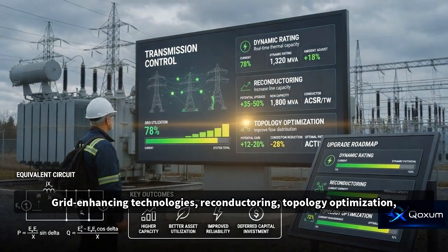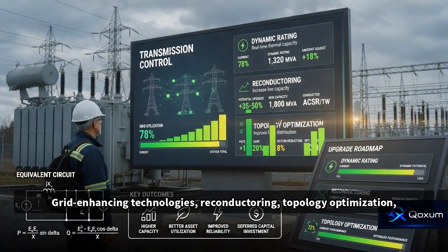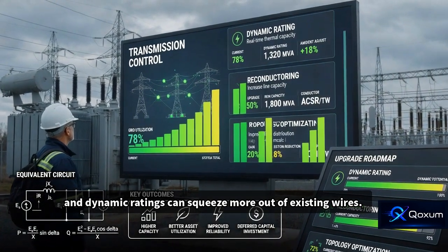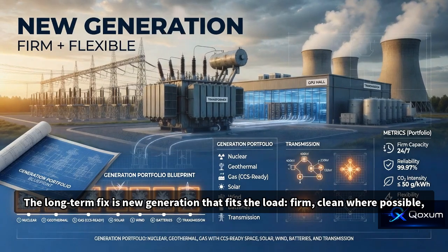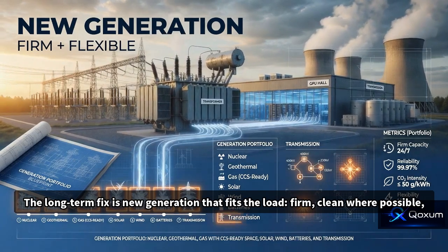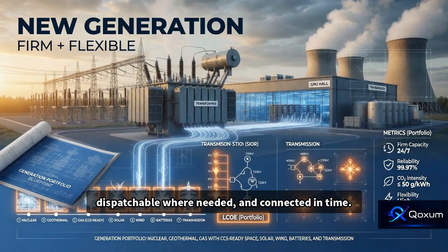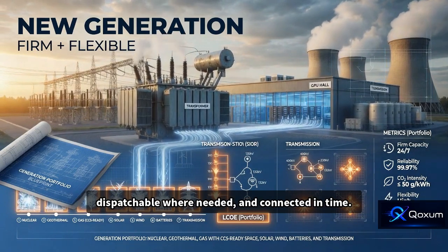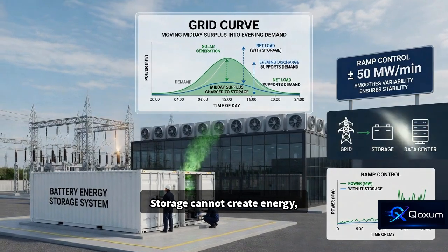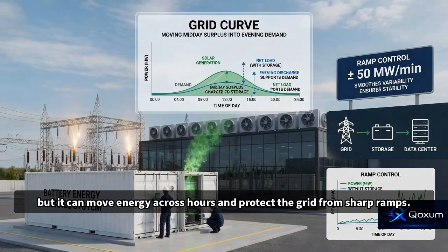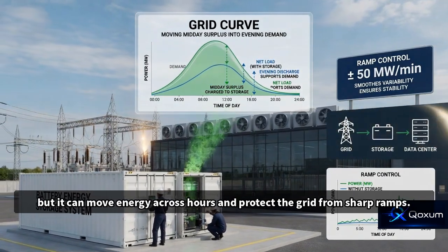Grid-enhancing technologies, reconductoring, topology optimization, and dynamic ratings can squeeze more out of existing wires. The long-term fix is new generation that fits the load: firm, clean where possible, dispatchable where needed, and connected in time. Storage cannot create energy, but it can move energy across hours and protect the grid from sharp ramps.